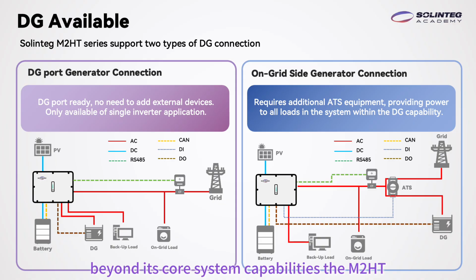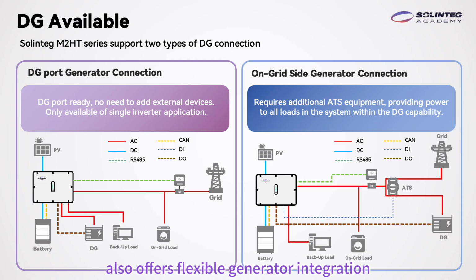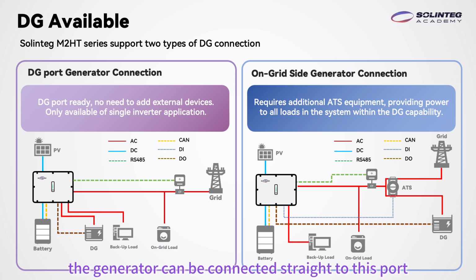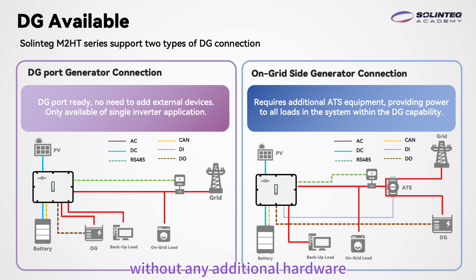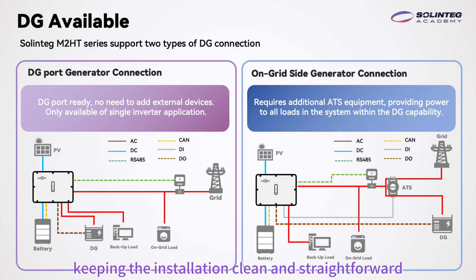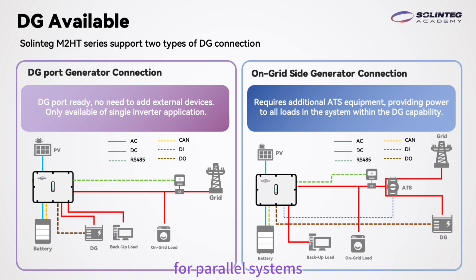Beyond its core system capabilities, the M2HT also offers flexible generator integration, an important feature for sites where grid reliability is a concern. The M2HT has a dedicated DG port built directly into the unit. In a single inverter setup, the generator can be connected straight to this port without any additional hardware, keeping the installation clean and straightforward. For parallel systems, or where greater flexibility is needed, the generator can alternatively be connected on the grid side through an ATS.